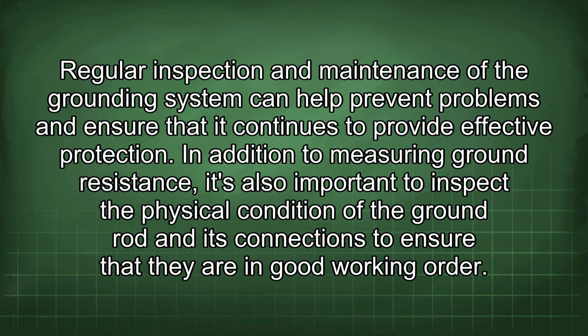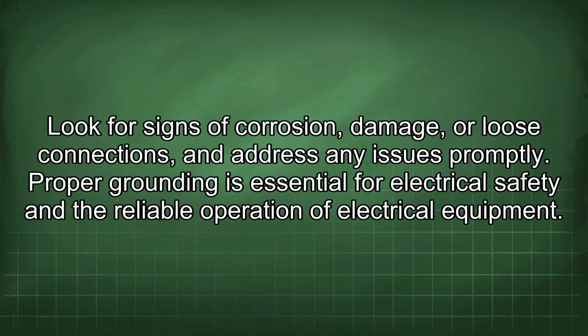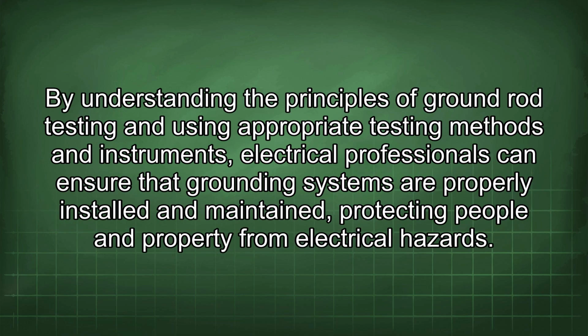protection. In addition to measuring ground resistance, it's also important to inspect the physical condition of the ground rod and its connections to ensure that they are in good working order. Look for signs of corrosion, damage, or loose connections, and address any issues promptly. Proper grounding is essential for electrical safety and the reliable operation of electrical equipment. By understanding the principles of ground rod testing and using appropriate testing methods and instruments, electrical professionals can ensure that grounding systems are properly installed and maintained, protecting people and property from electrical hazards.